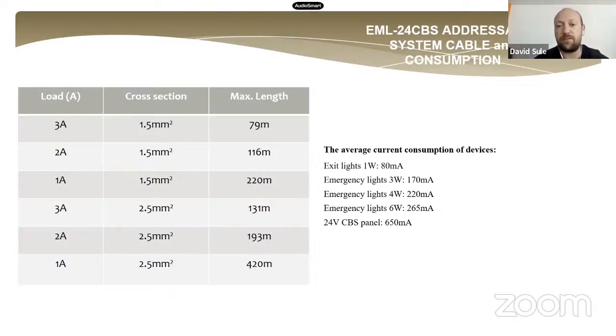So you can change the drivers inside, but after the commissioning, the addressable drivers in the light need to stay on the same circuit as before, because the panel will check the address of the lights. If we need to change any driver or add new lights into the system, we can do it easily with the programming software. We just have to click on a search new light button, and the panel will search only the new addresses. It needs just a couple of seconds, and it will show in a list.